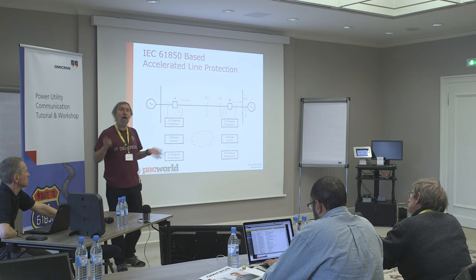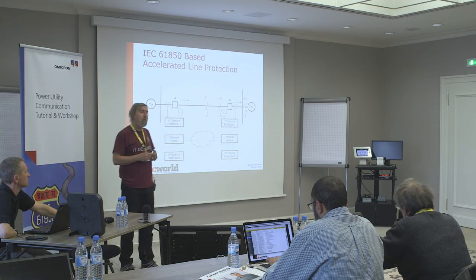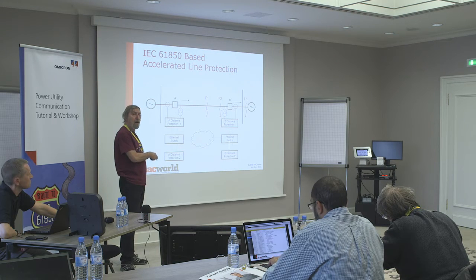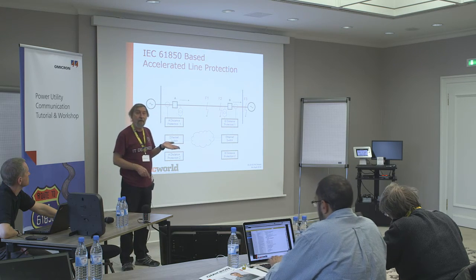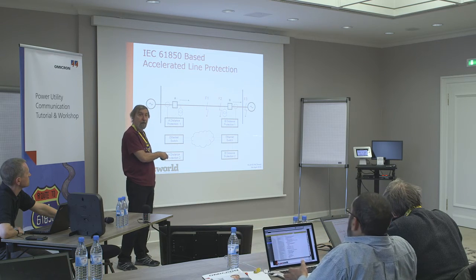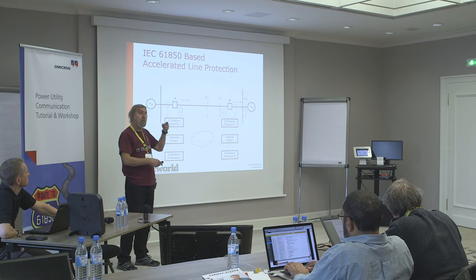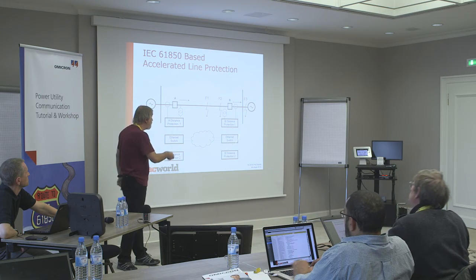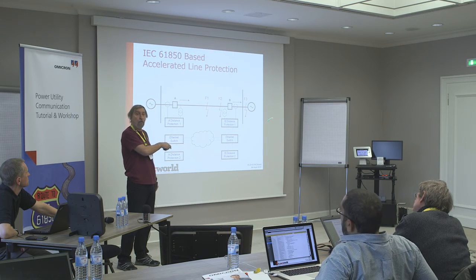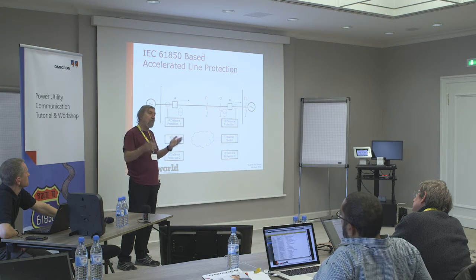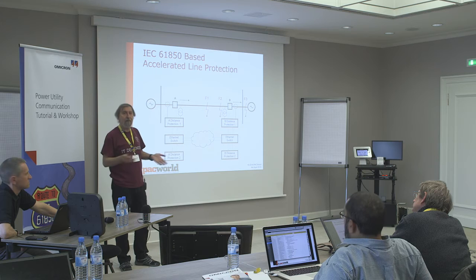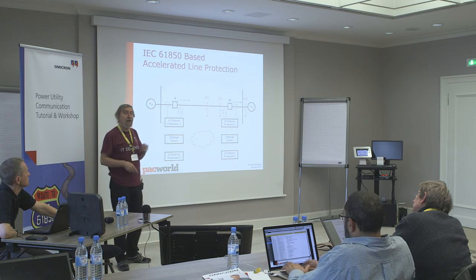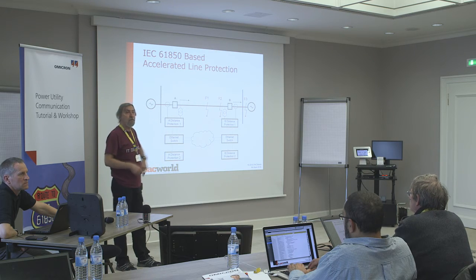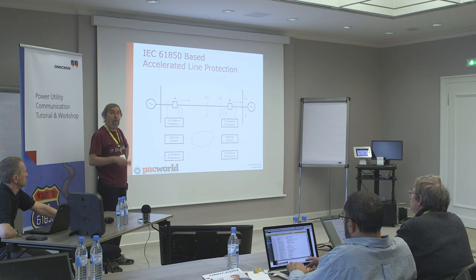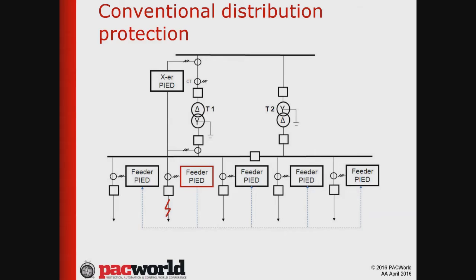Now people say, but what about cybersecurity? Well, keep in mind, even if somebody hacks into the system and sends a fake GOOSE message, it's not going to result in anything. Why? Because we have a local supervision. It is called a permissive signal. It's a signal that is permitting the accelerated tripping. But if I don't see a fault with this relay that is seeing a fault in zone 2, I'm not going to trip. And on top of that, the routable GOOSE has cybersecurity in it, etc. So I'm just giving you an idea of another solution that can actually help improve the performance without any additional cost for communications equipment.